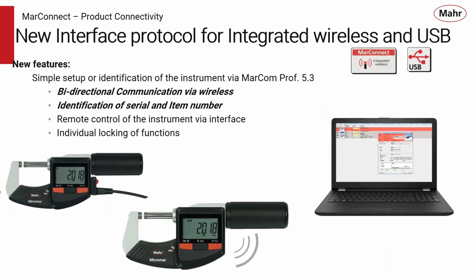And whether it be the wired or the wireless products, we have that bidirectional communication, getting the identification, serial number and item number, but we also have the ability to have a little bit more control of that product. Through MarCom, we're now able to control auto zeroing, locking out features, setting tolerances and so forth.